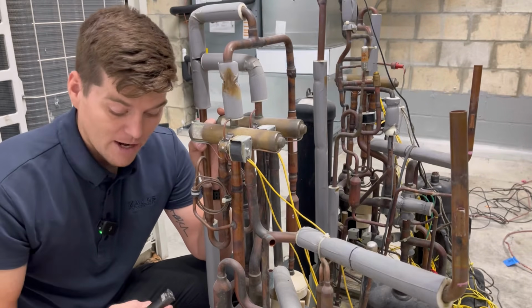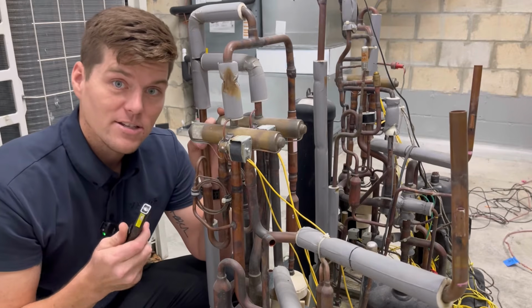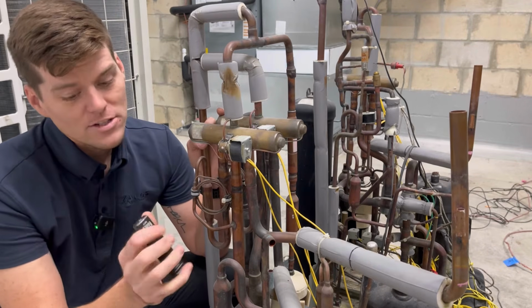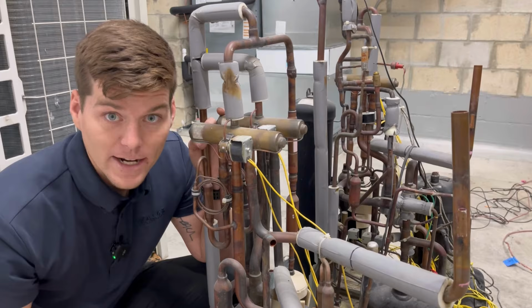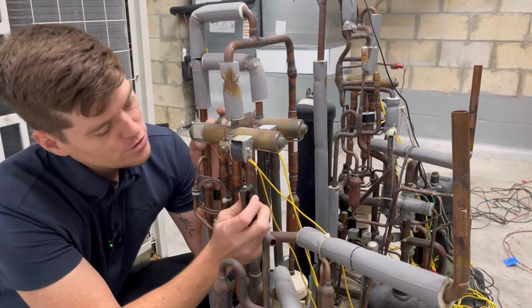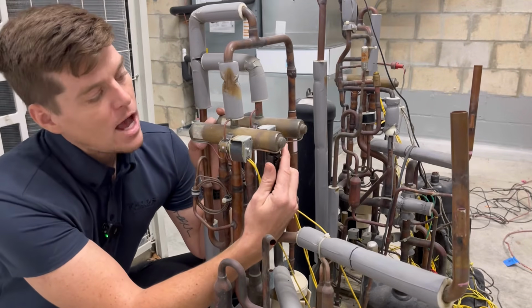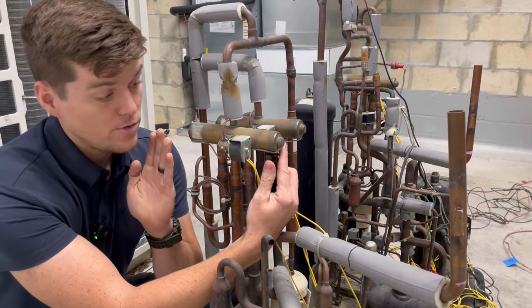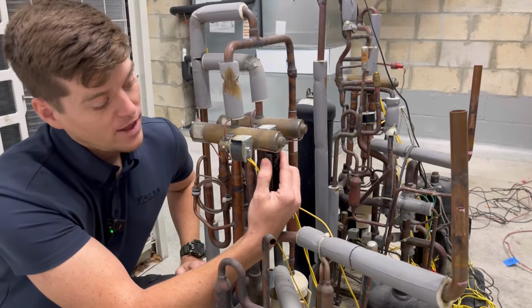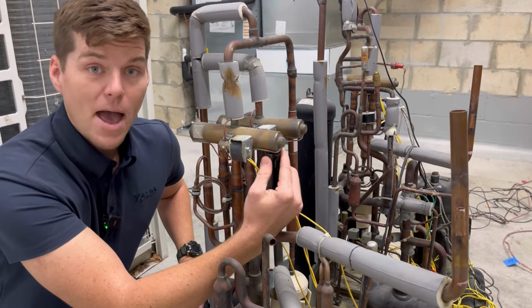Well, I actually happen to have one of Klein's newer flashlights I got off TruTech Tools. It has a strong magnet on the base. Now, any strong magnet will do, not a weak magnet. And what you'll do here is we'll check on the end. Now, if the four-way valve was shifted all the way to the right-hand side, you'll find that it sticks, and we've got no magnetism here.